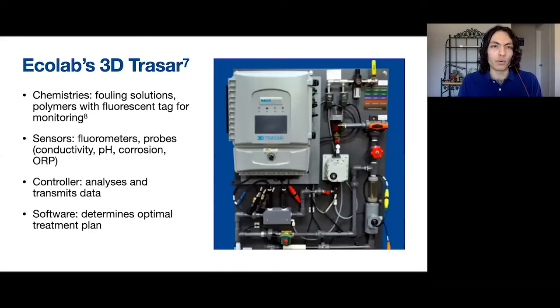One way to automate the cooling water management process is to use Ecolab's 3D TRASAR technology, which is a combination of chemistries, sensors, controllers, and software. The chemistries are the fouling solutions that I mentioned in the previous slide, but these chemistries can also be polymers with a fluorescent tag that allow for monitoring them throughout the whole system. And the way we monitor this is using a fluorometer, which is a sensor that reads fluorescence.